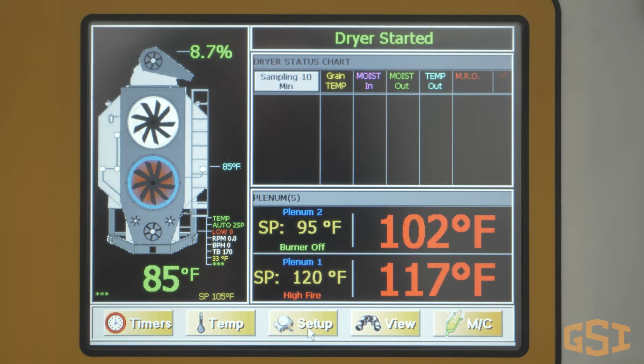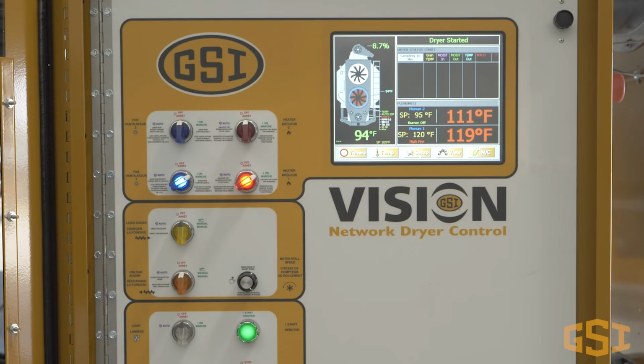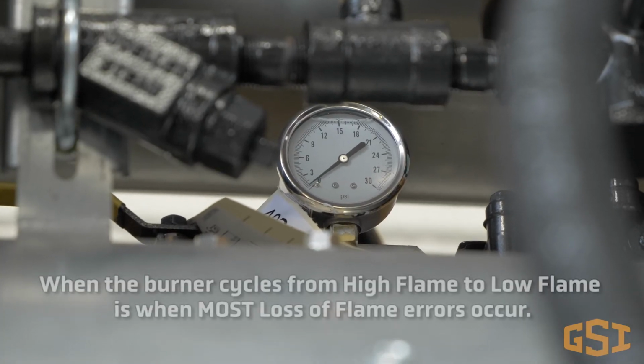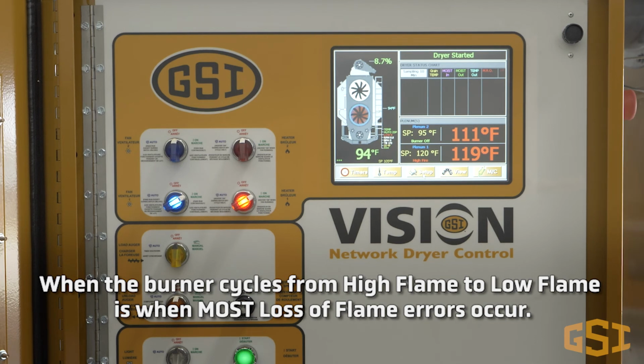Continue to monitor the burner light, especially when the actual temperature inside the plenum reaches the 120 degree set point, because when the temperature matches the set point, the fuel pressure to the burner is reduced and the size of the flame is reduced. Now that you have reached the plenum set point and the vision controls have reduced the fuel pressure, you will see most loss of flame failure. The size of the flame has been reduced, so there is less flame in contact with the flame probe. Watching the burner light when the burner is in low flame is especially important. Remember, the light should not blink or go out.